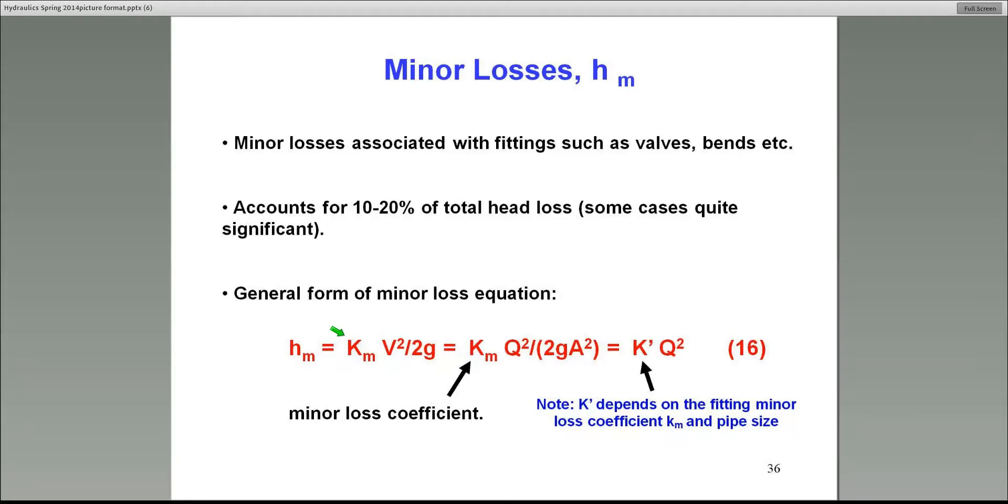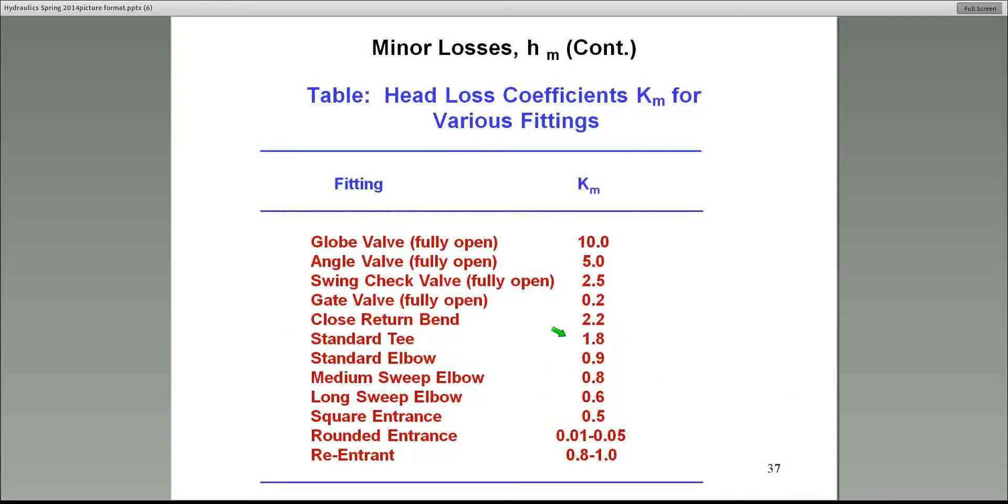Now, I can rearrange this also into the same form as we did for the friction loss. And that is in terms of Q, the discharge. Recognizing the fact that Q over A is velocity, and therefore, manipulate that equation and finally into this form, where K prime is now a function, not only of K_m, but also the cross-sectional area of the pipe, which is okay because most of the time that is true. It depends on the fitting, which pipe it's in, the size of that pipe is important also in the head loss situation.